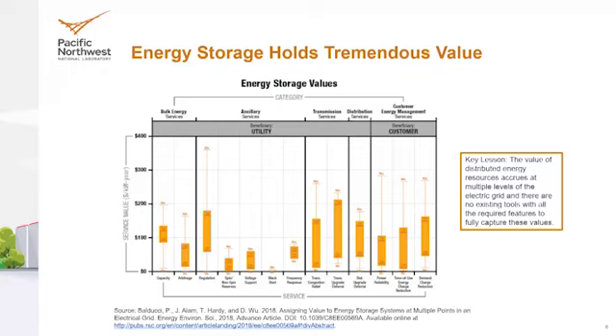Some of the values, much less so. But energy storage systems are extraordinarily efficient at providing frequency regulation. That's where the load and generation is brought into balance. Energy storage systems are exceptional at following fast fluctuating signals that are shared with markets or regional operators. And also resource adequacy or capacity. This is based on the cost of a new entrant, the next best alternative of providing this service. They tend to aggregate around the $80 to $120 per kilowatt per year value.